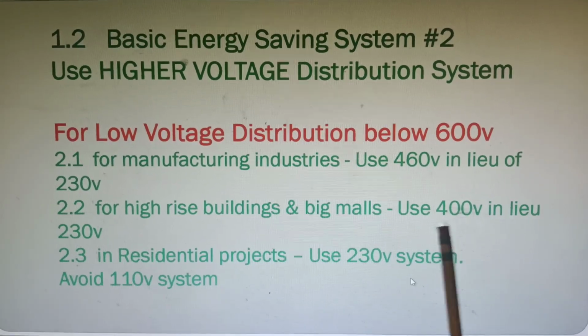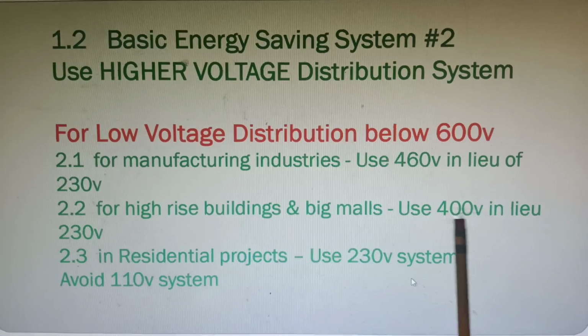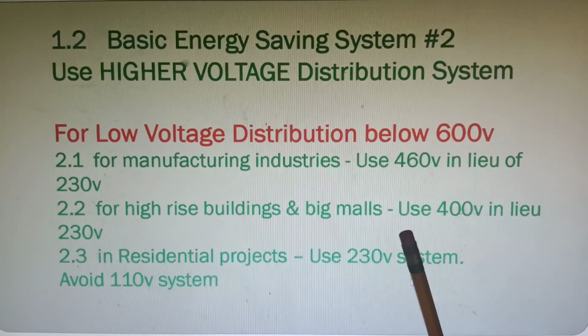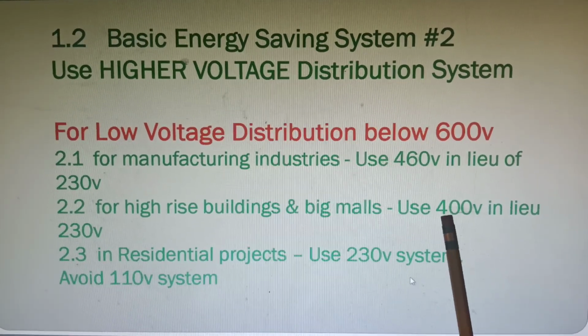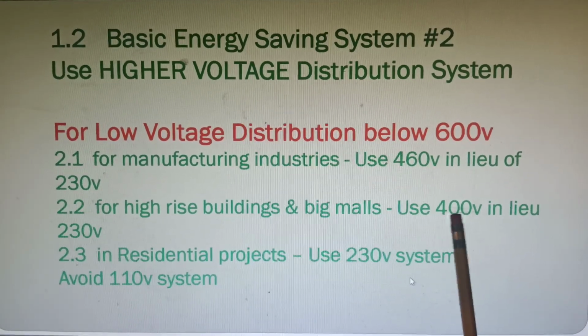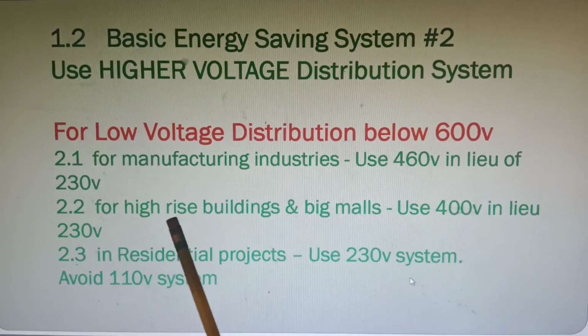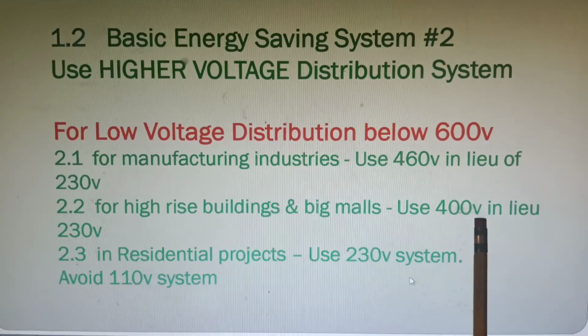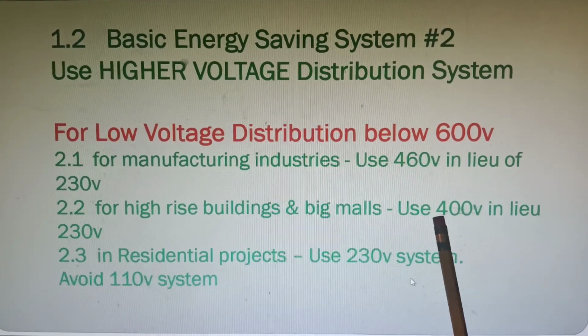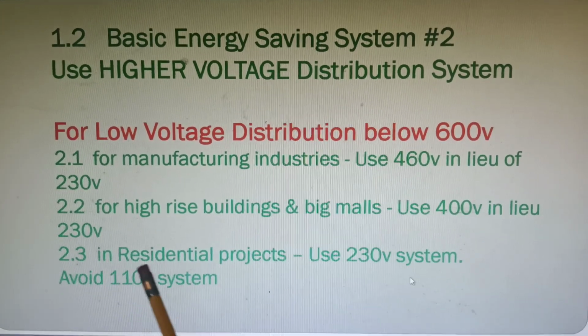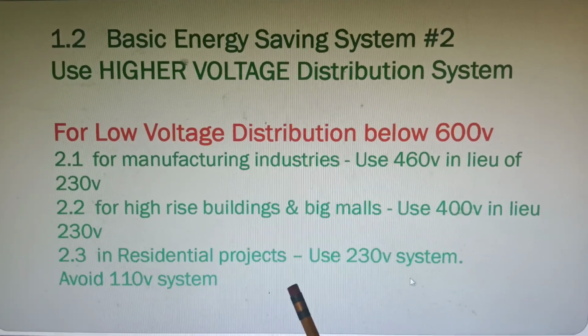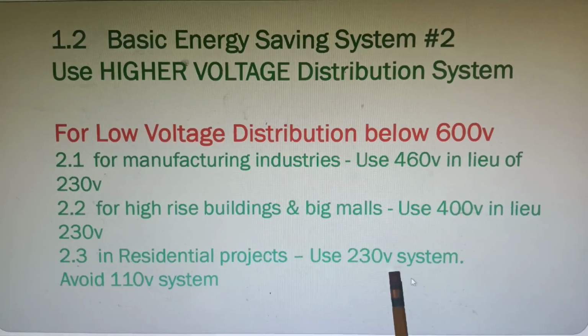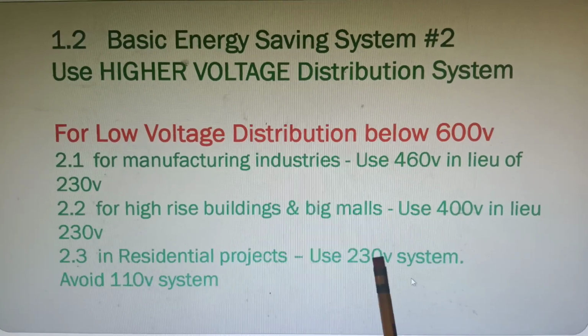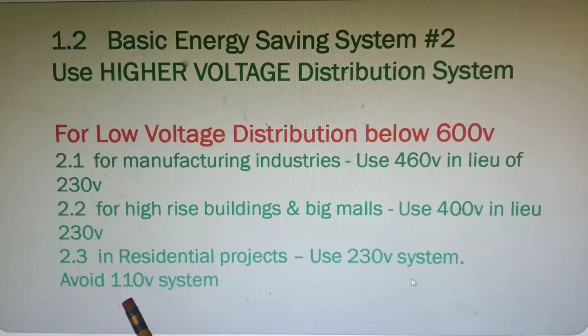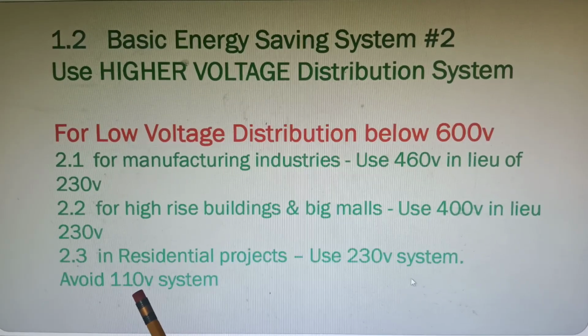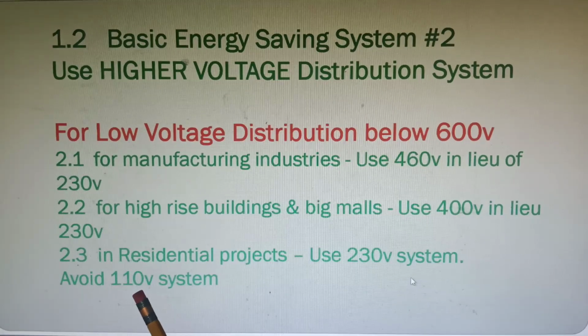Of course, the bigger loads like the big motors, the fire pumps, the elevator motors, the water pumps, the air conditioning, and all other loads in this kind of buildings, high-rise and big malls, will be at 400 volts. Okay. In 2.3, we mentioned that in residential areas or projects, it's much better to have a 230 volt system than a 110 volt system. Definitely, because in the 110 volt system, the current will be much bigger.